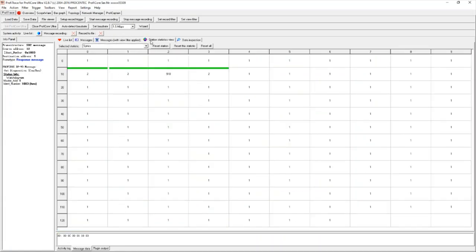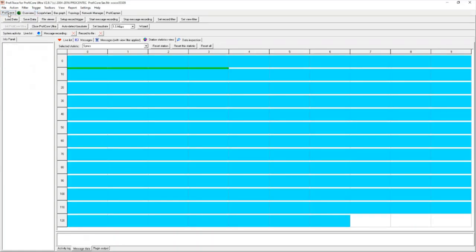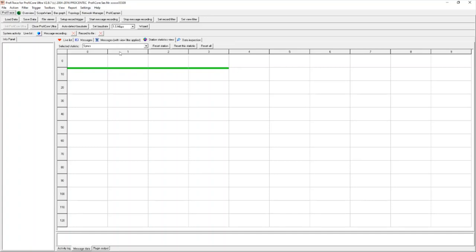I then have my station statistics view. Whenever connecting to a new network or a new segment, or finishing analysis of a certain part of the network, always hit 'File New.' This clears the network buffer and starts you on a fresh canvas so previous recordings do not misinterpret future data. There are a couple of very useful statistics we utilize to identify faults in Profibus networks.